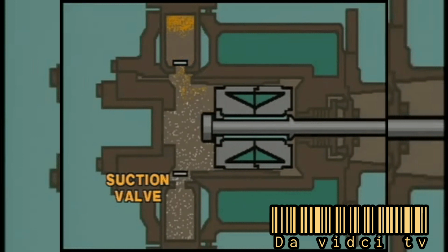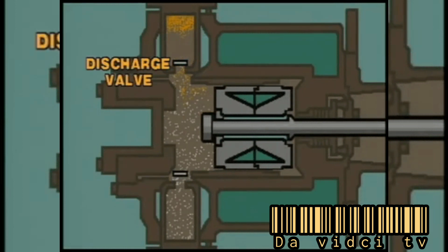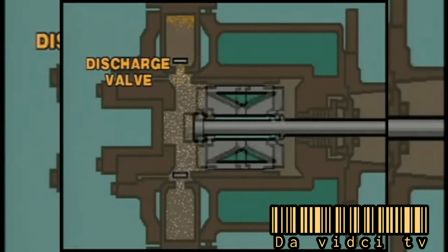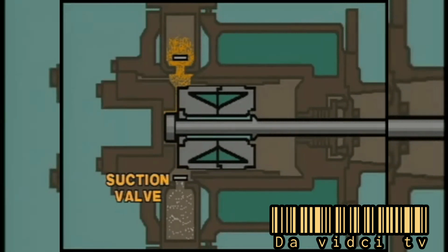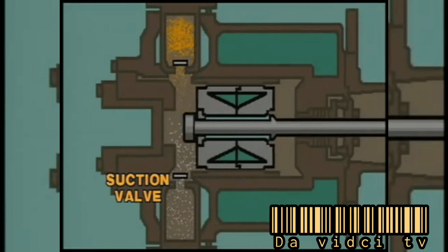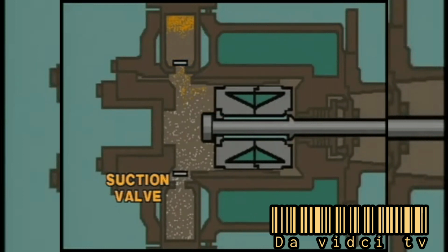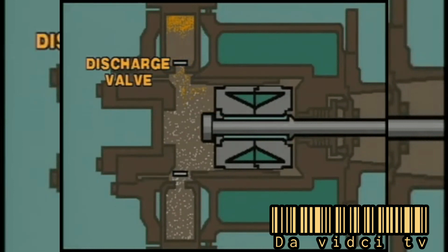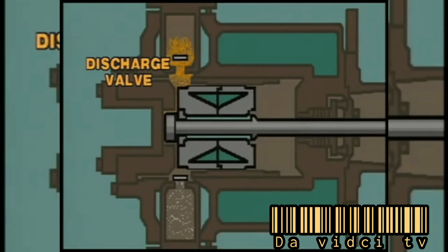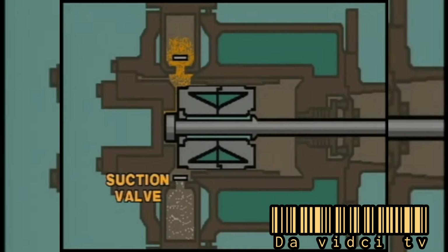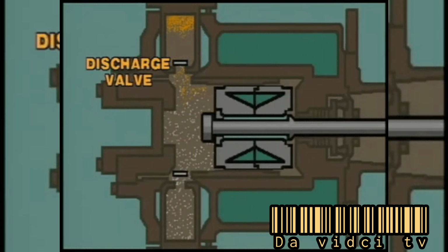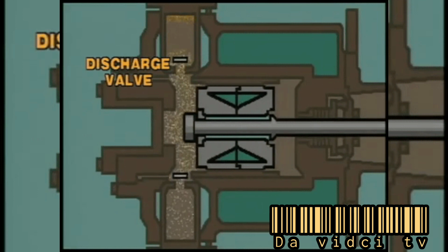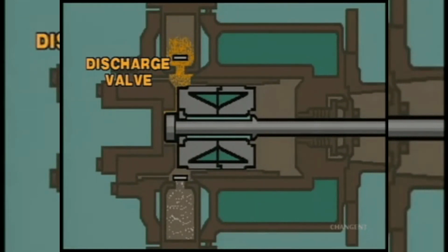Mechanical performance. Due to the many moving parts of a conventional reciprocating compressor, speed variation and flow capacity control make it difficult to avoid vibration problems. Each moving part has its own natural vibration frequency and high cycle fatigue limitation. The LMRC uses fewer moving parts, and thus, it will be easier to design the system to avoid coincidence with component mechanical natural frequencies.